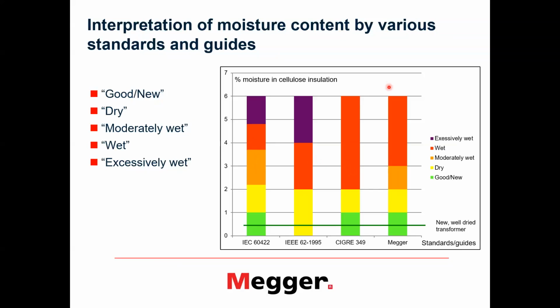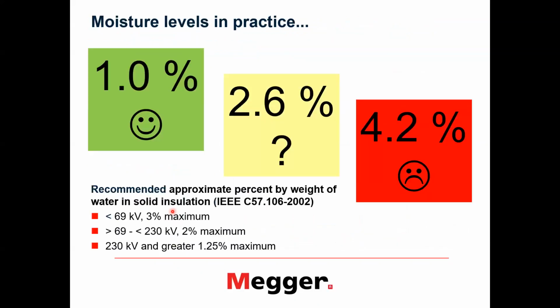And the last column is the Megger guide, so to speak, saying good new is up to 1%, dry is up to 2%, 2 to 3 is moderately wet, and everything above 3% is a wet transformer. So these are the guides which we have implemented in our HYDAX software, which measures the moisture in the transformer.